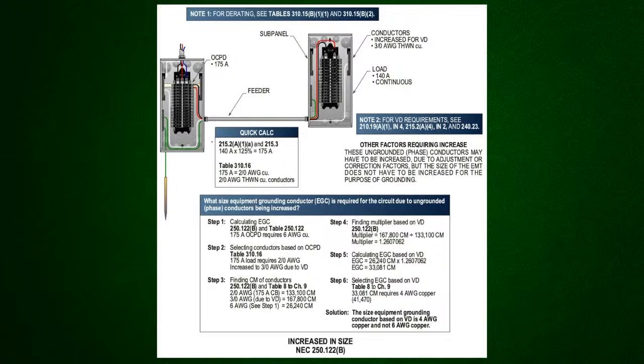All right. Yeah. Now, what you would do, and you'll see this is exactly what I've been talking about. If you look at table 250.122, it'll tell you a 175 amp overcurrent device requires a number 6 copper equipment grounding conductor. Okay. Right. Now, if I decide I need to kick this up to 3/0, you would look at step 3, and we tell you to go look at chapter 9, table 8. For a 2/0 conductor, you get the circular mil. It's 133,100 circular mil. And for a 3/0 conductor, it's 167,800 circular mil.